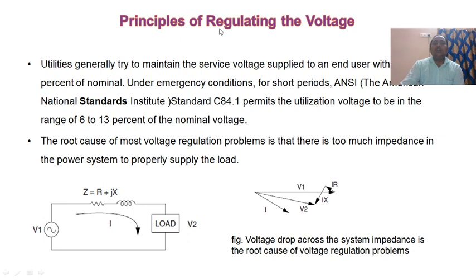So what is the principle of regulating the voltage? The principle of regulating voltage means utilities generally try to maintain the service voltage supplied to end users within plus or minus 5% of nominal. So the variation must be between plus or minus 5, not more than 5, not less than 5. So if the reference voltage is 100 volts, the voltage must lie between 105 and 95 volts. Under emergency conditions for short periods, ANSI, the American National Standards Institute, C84.1 permits the utilization voltage to be in the range of 6 to 13% of nominal voltage.